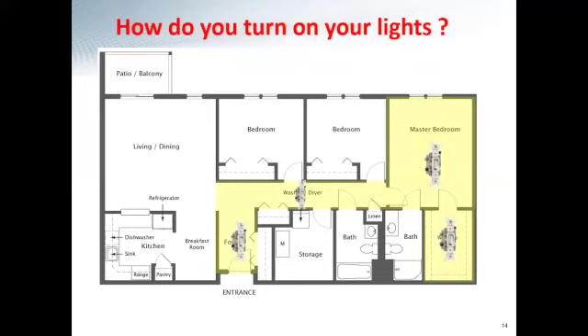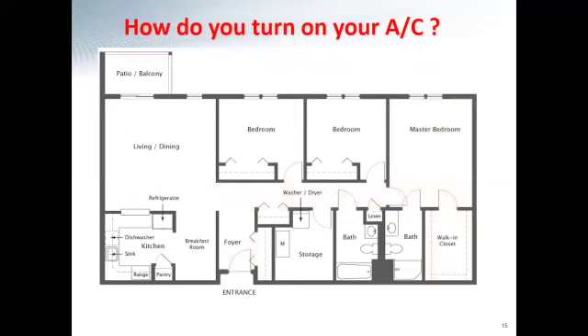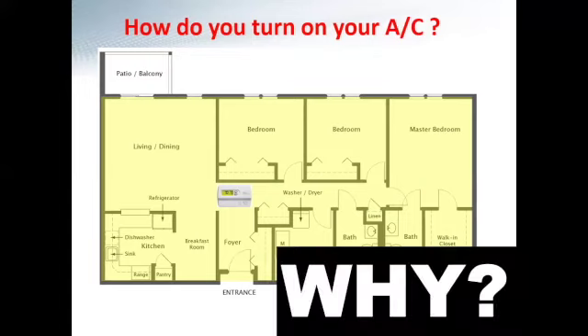It makes no sense to have one switch for your entire house, turn all of the lights on or turn all of them off. I know growing up, I always got in trouble if I turned on or left on lights in the space that I wasn't in. That's very similar to how we look at using your VRF systems and AC in general. So how do you turn your AC on typically in a house or any kind of application that you might see? You walk in, there's going to be one centralized thermostat in the foyer, and then you're going to cool or heat that entire space to a single set point when very typically you're not going to be using almost all of it. So why would we do this?